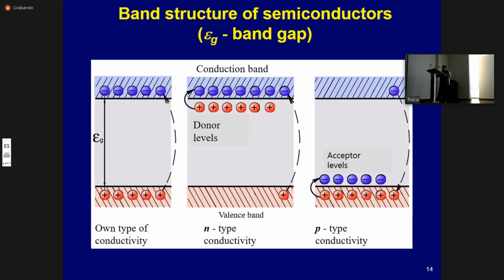In contrast to the ionization chamber, current flows through a semiconductor detector even in the absence of ionizing radiation. The presence of this background current in both intrinsic and impurity semiconductors makes them unsuitable for dosimetry purposes.